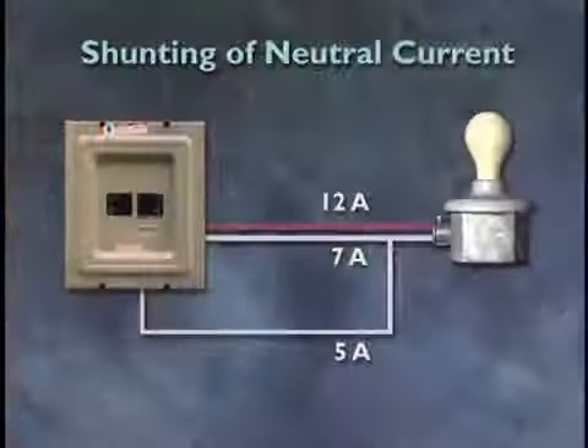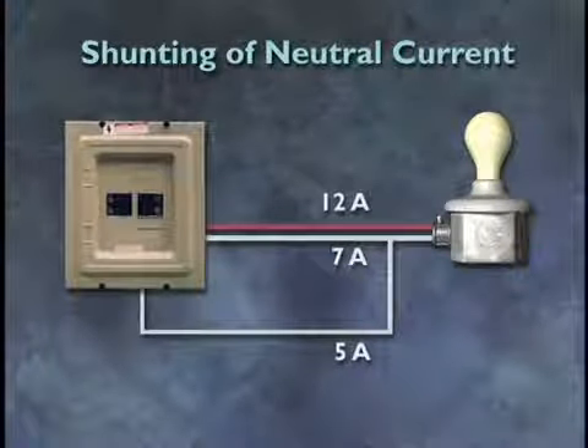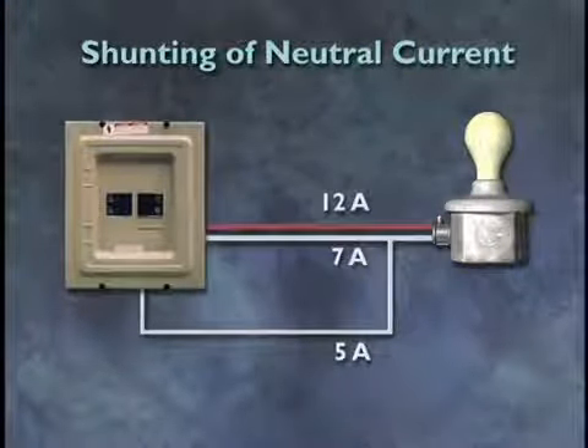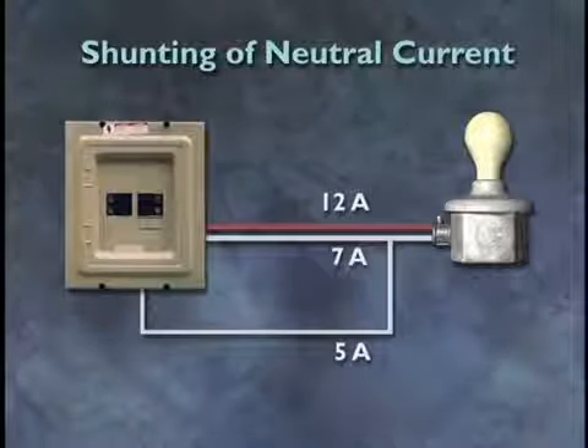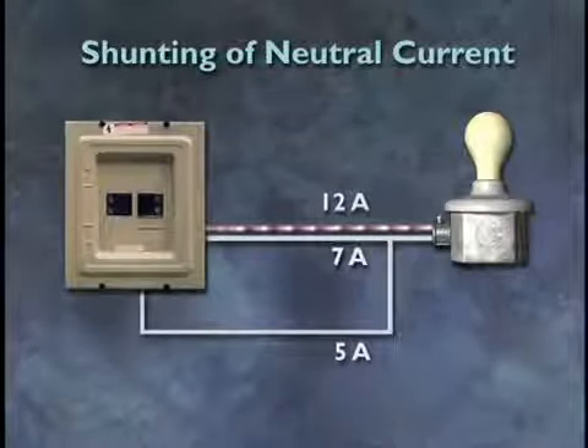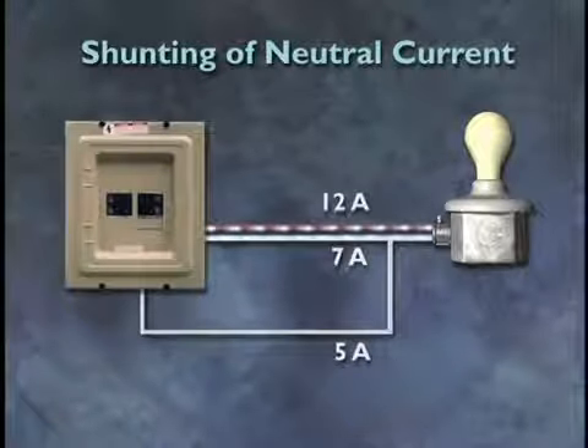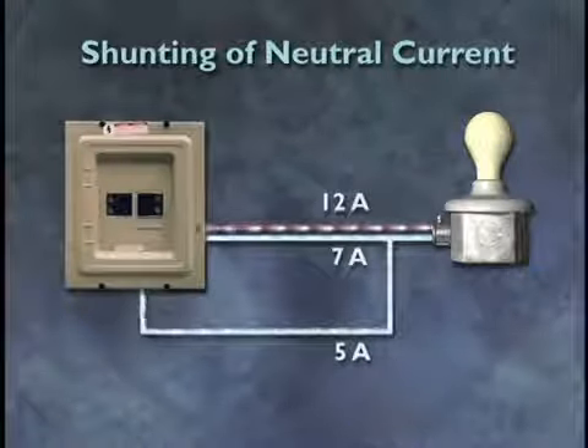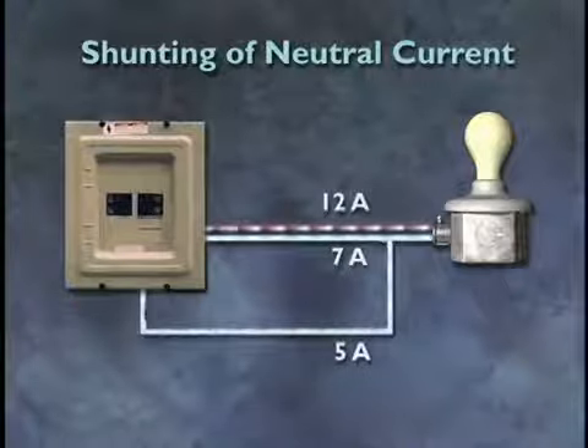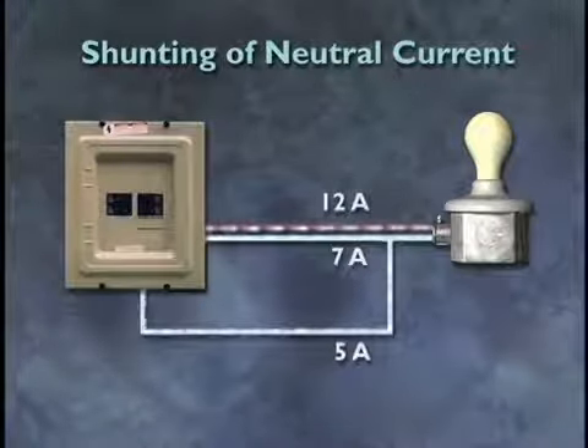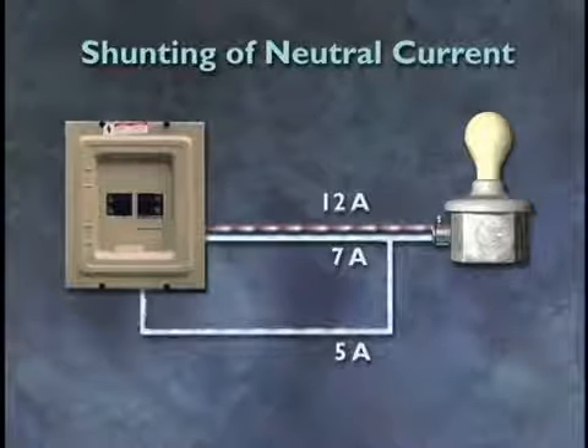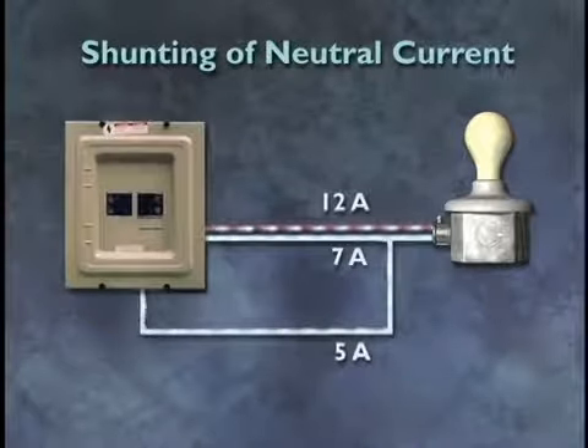But how are we going to get an unequal amount of current in the return neutral? Let's look at a diagram of a circuit where an extra neutral has been added in parallel with the first. The neutral return current now has 2 paths, and the current divides in accordance with the relative impedance of each path. In this graphic, we've assumed a higher impedance in the second path. The net current is 5 amps from both parts of the circuit. 12 minus 7 equals 5. When neutral current is shunted, the net currents on both paths will be the same.